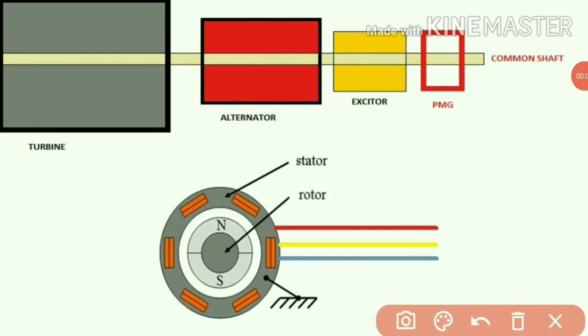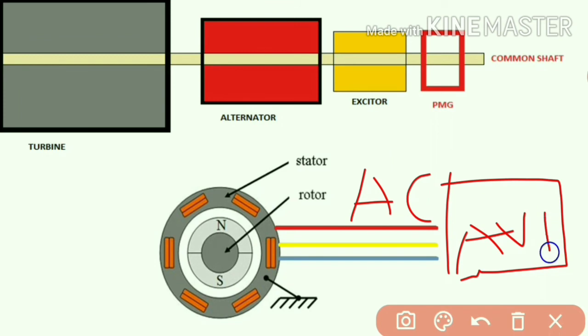So this voltage generated by PMG is in AC form and it is fed to the AVR. Guys, this AVR converts this AC into DC and supplies the exciter field.